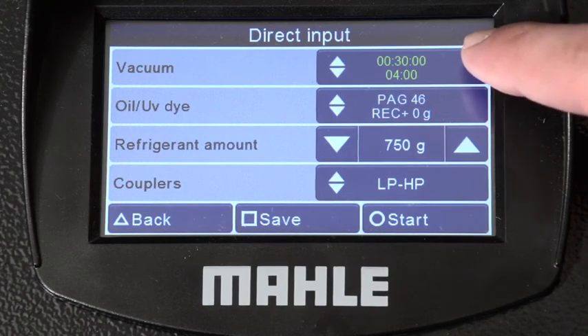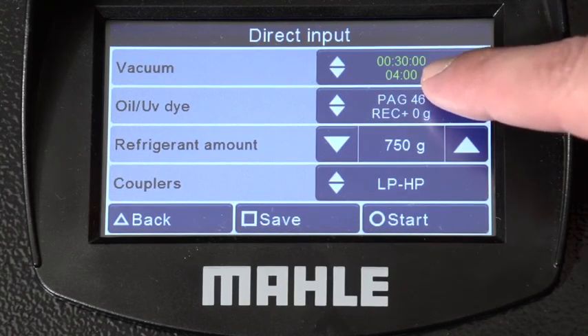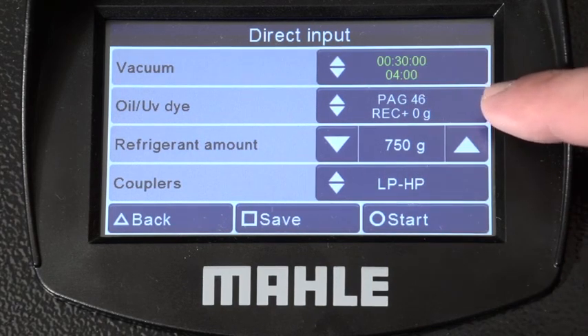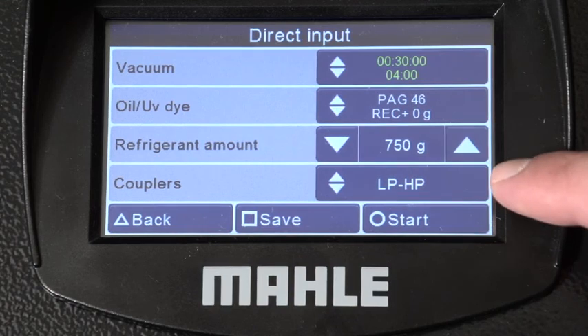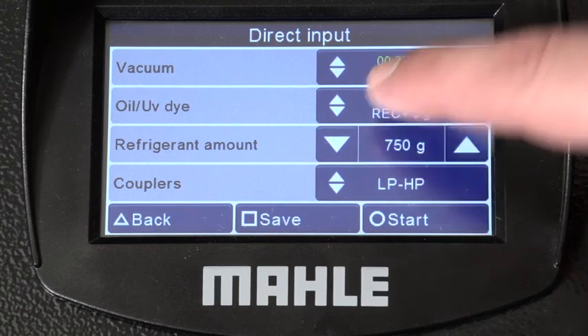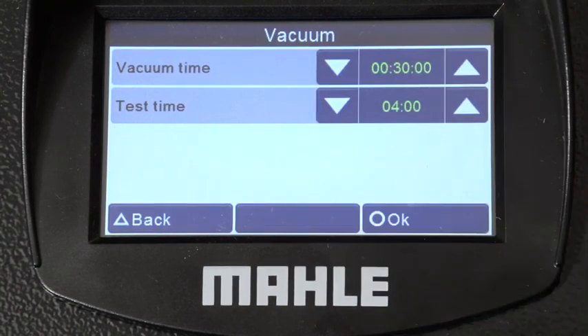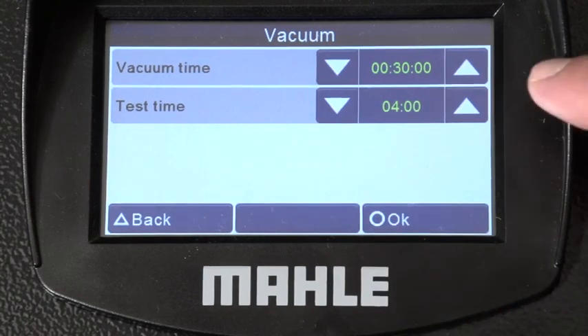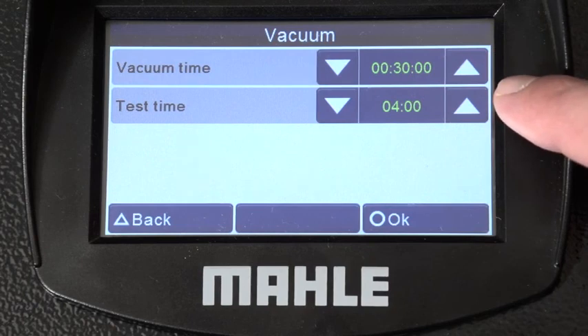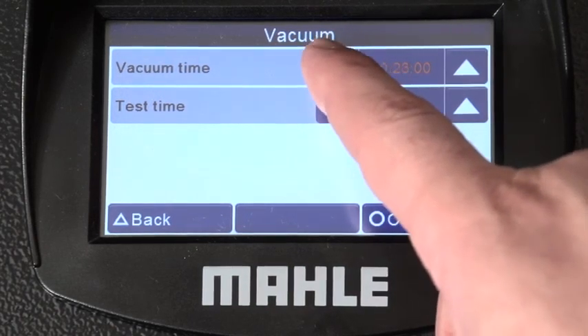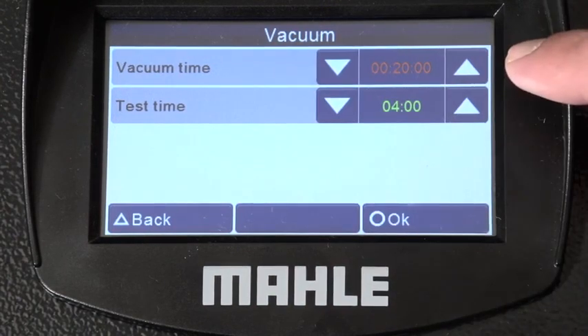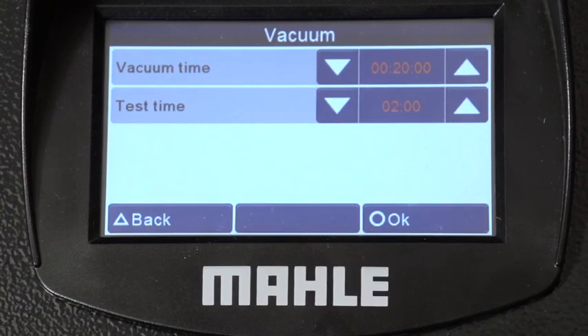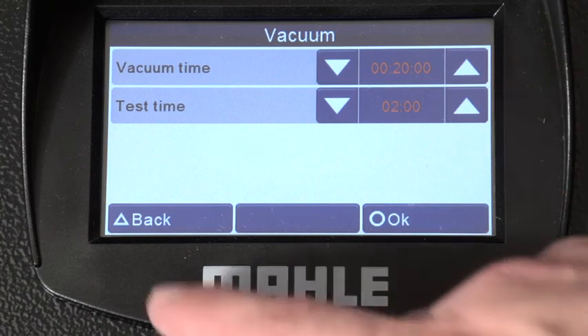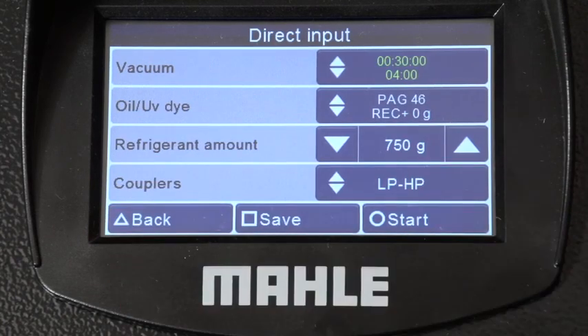We can set our vacuum time. Top number is vacuum time, bottom number is hold time. Our oil type, refrigerant amount, and the couplers we are charging through and recovering through. The vacuum time, if I touch that, the numbers are green here. This is the minimum value the machine wants to see. We can go below that, as the letters turn red, same with test time. We can go below 4 minutes. It will still allow the service to happen. It'll just give you a prompt here that says you're below the minimum.